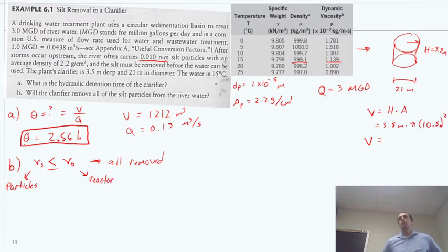And typically for a sedimentation problem, at the end of the day, what we do is compare those two, comparing the particles to the reactor, and in some cases we're designing a reactor for a particular type of particle. Okay, so let's start with V naught. That's a little bit simpler. Critical settling velocity, we said this is Q over A_B, the area of our basin.